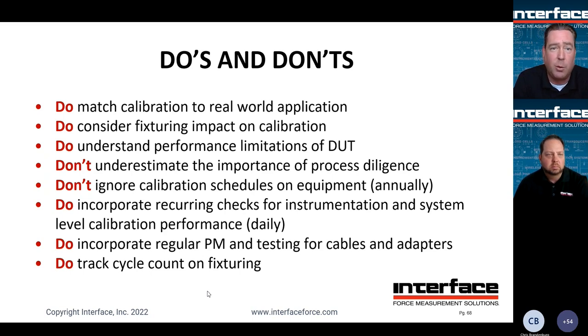Another one that comes up pretty frequently: do you understand performance limitations of the device under test? So is the calibration selected appropriate for the DUT being calibrated? For example, if you have a small load button type device that is 0.5% accuracy, is it worth going to the trouble of performing an E74 calibration on said load button when the repeatability may not be sufficient to justify that type of calibration?